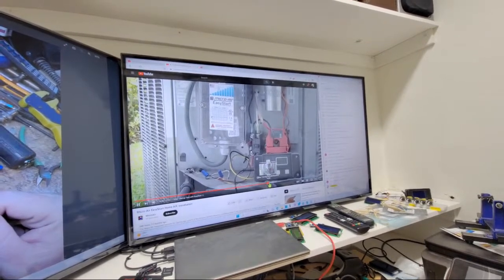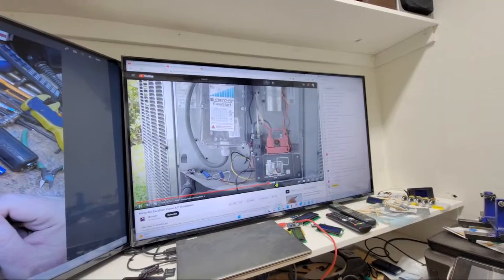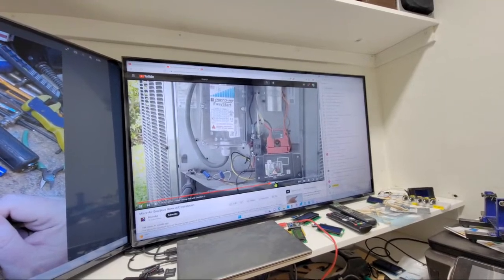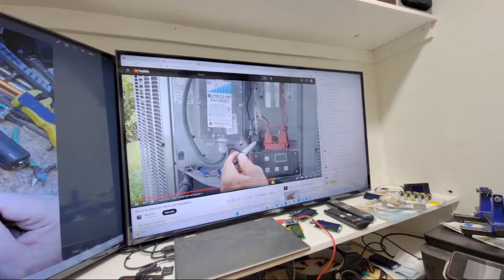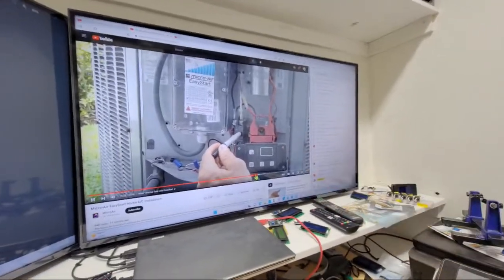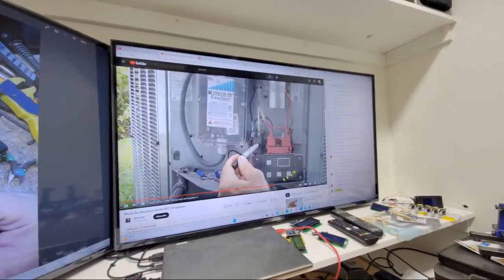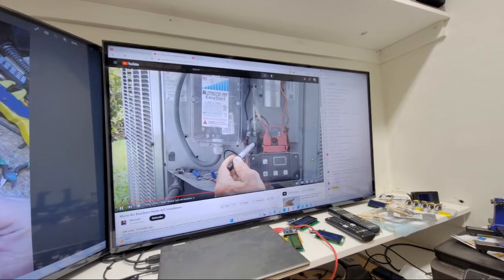The very first 5 starts that Easy Start carries out, it optimizes its internal parameters, and here we go. You got fan at 4 amps. What you see is that through the run capacitor, 5 seconds later, Easy Start kicks in.